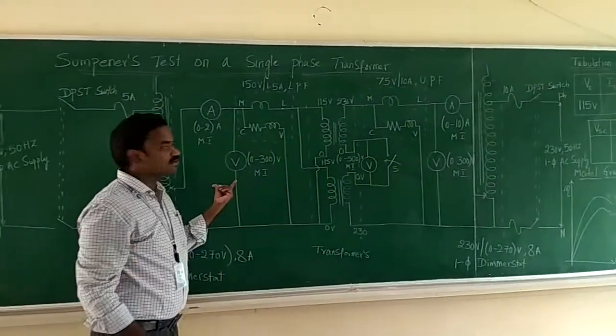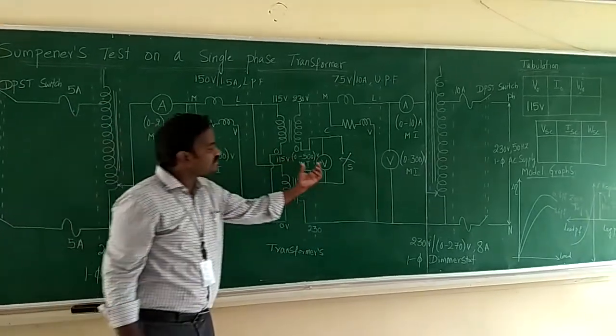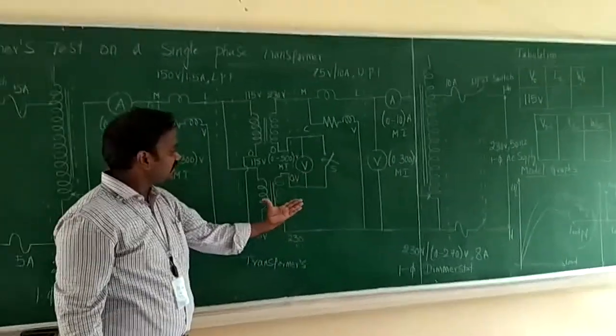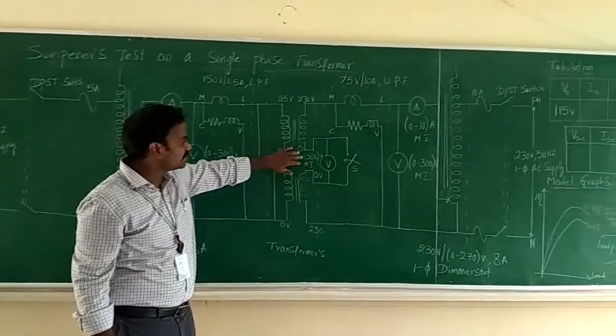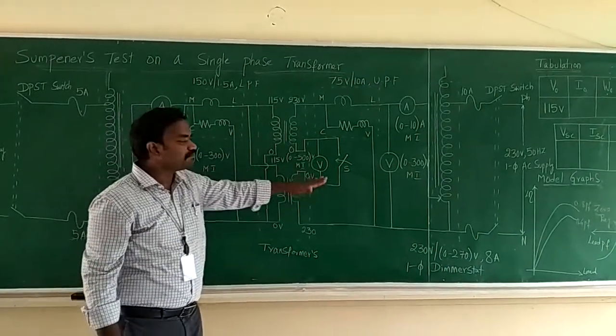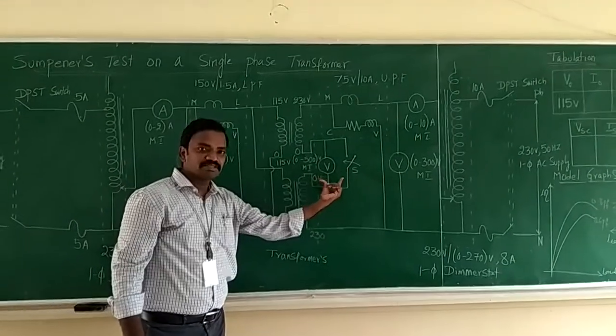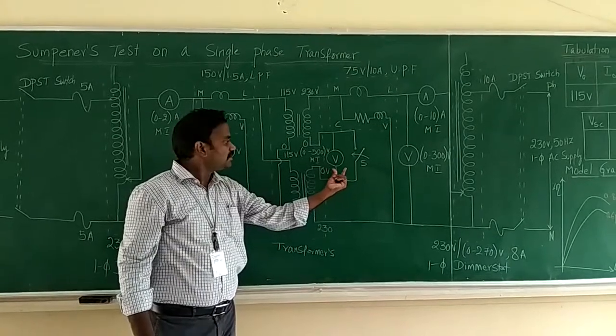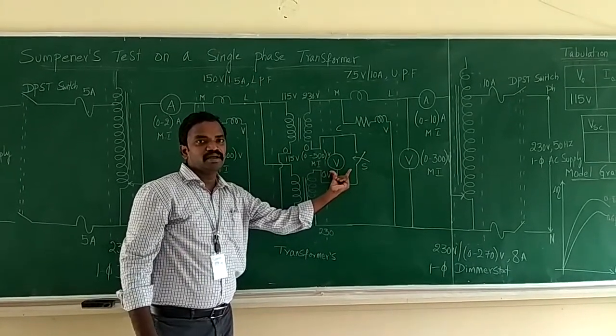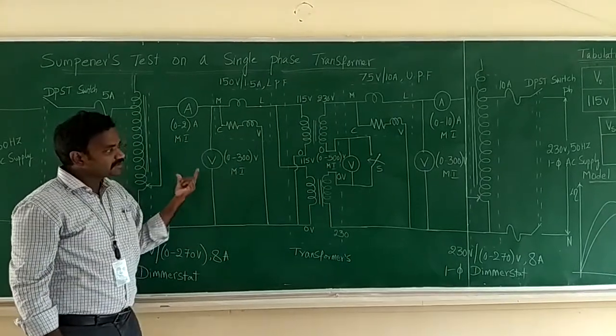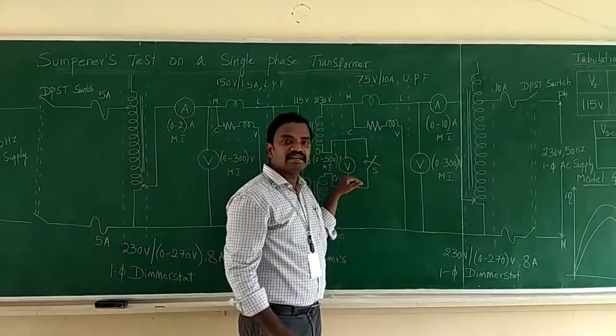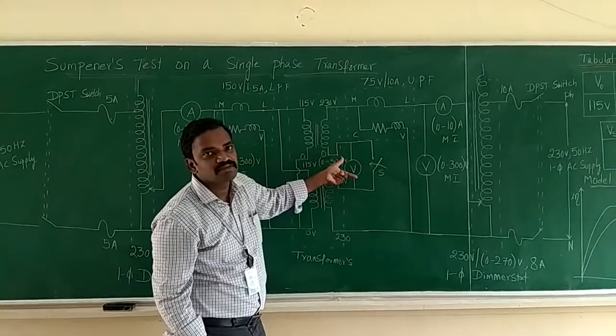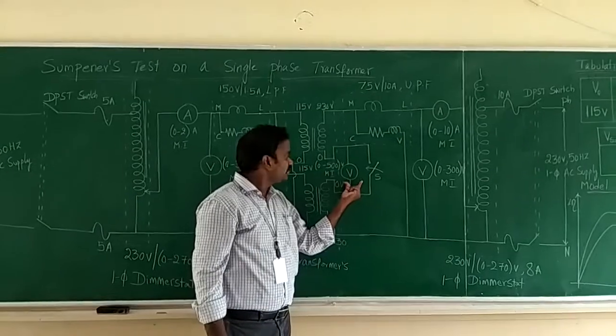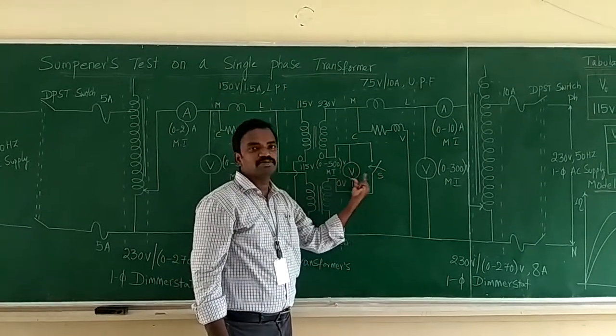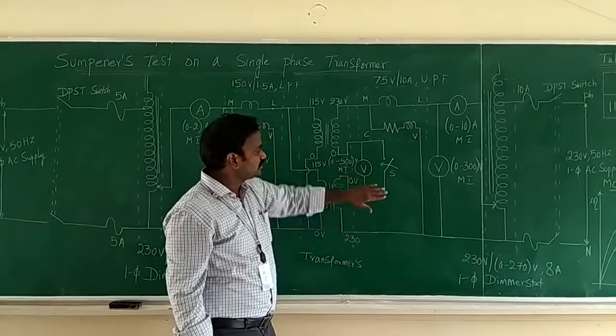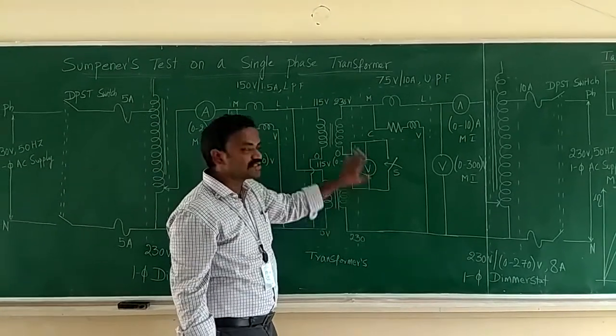By applying the rated voltage, we check our secondary side voltmeter. Here, the transformer secondary windings have to be connected in series with phase opposition. That can be shown by this voltmeter. How will it happen? This voltmeter will show a zero reading when the rated voltage is applied at the primary side. If it is not happening, we have to interchange these voltage terminals. When this voltmeter shows the zero reading, then the switch has to be closed. After this switch is closed, the transformers are connected.